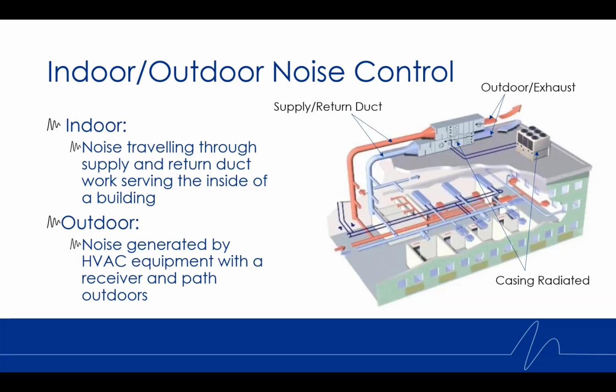So when we talk about indoor noise control, this is typically going to be noise that's traveling either through the supply or the return duct, typically from an air handling unit, rooftop unit, makeup air unit, something of that nature. But it can also be for fan coil units, VAV boxes, smaller equipment as well. It's essentially anytime there is a sound path traveling through the air, typically through the ductwork, into an indoor space. When we talk about outdoor or environmental noise control, this is when the sound path and the person receiving the noise is outdoors. So this could be the outdoor air intake or the exhaust air from one of those units, or even the casing radiated noise.